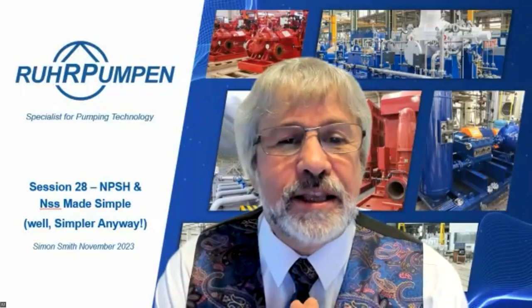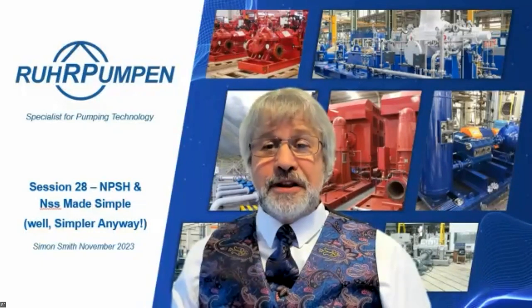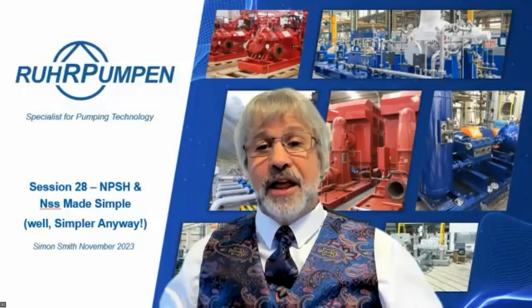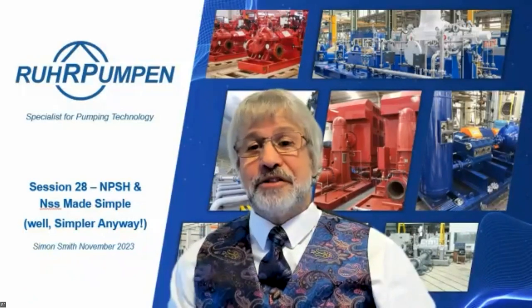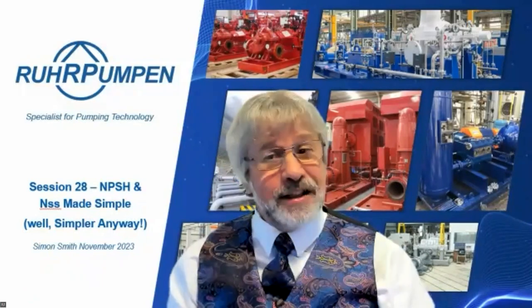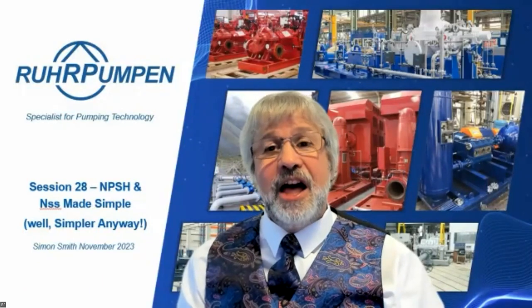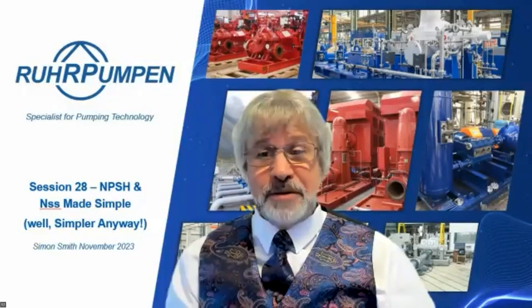Mikolaj Juskoviak asks: what are some golden rules for designing systems to avoid cavitation and achieving the best possible efficiency? As a pump vendor, what I want customers to do is raise suction vessels high enough or raise the pressure in their system so there's plenty of NPSH available. I know that can't always be done, so it's a compromise. I tell you my best possible NPSHr, you tell me your best possible NPSHa, and we look at what we can do. Maybe you need a pump with a slightly higher suction specific speed of 13,000 - a modern design - or maybe you need to switch to a VS6 type submerged suction pump.